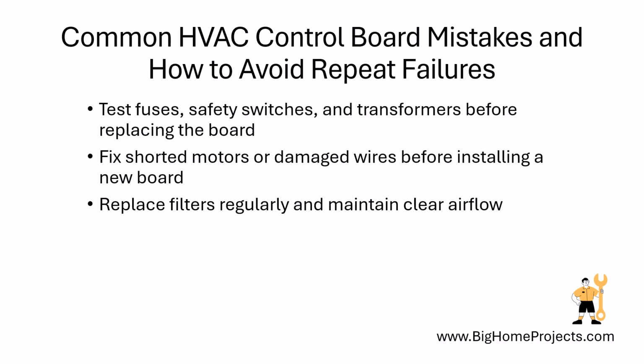Another mistake is installing a replacement board without fixing the shorted motor or damaged wire that destroyed the original, so find and correct the cause before powering the new board. People also assume a dirty filter directly burns out the board, but it usually causes overheating that stresses several parts over time, so replace filters regularly and keep airflow clear.